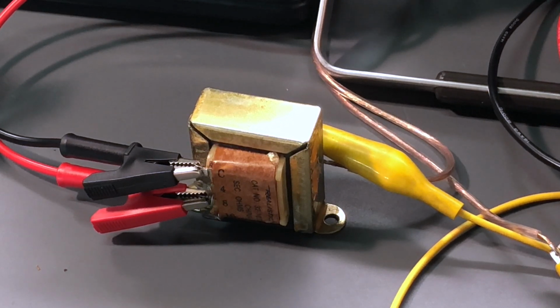So now enters the 70 volt system. It's a high impedance system, meaning the voltage is higher - it's 70 volts. As we saw before, when the amplifier was hitting its maximum wattage on the output, it was about 35, just close to 36 volts, and we were getting 160 watts.